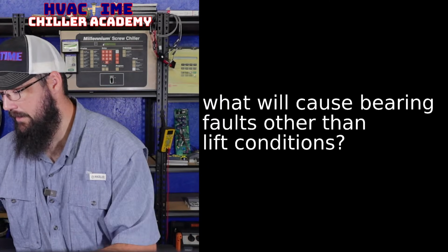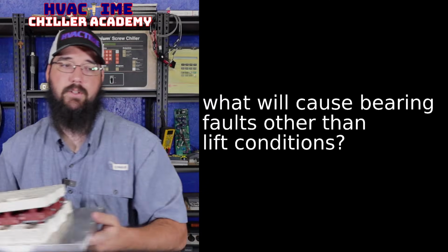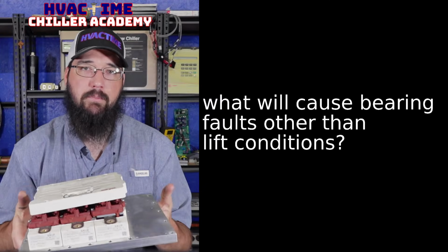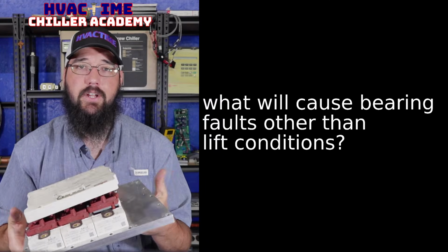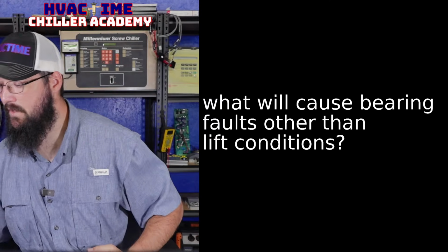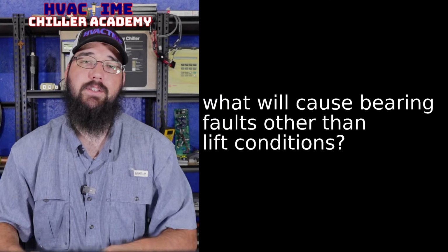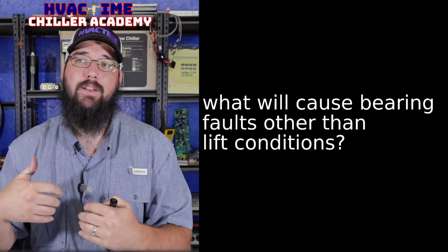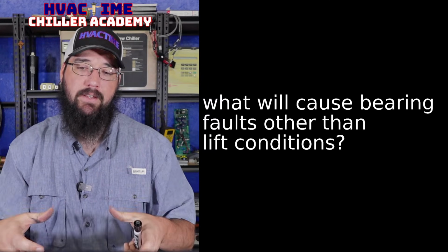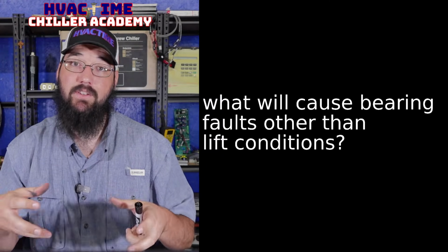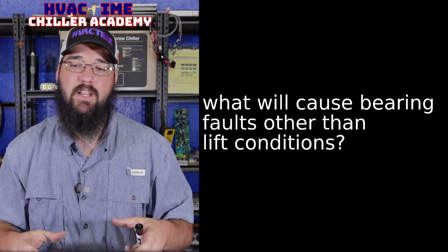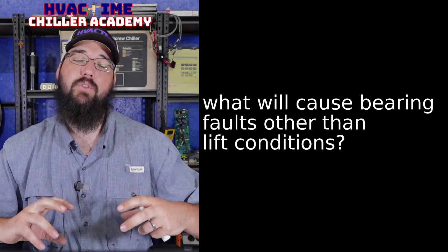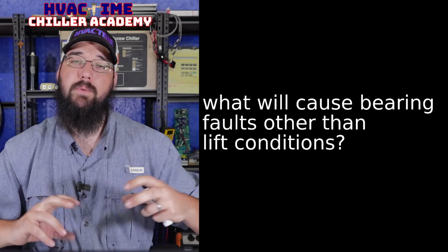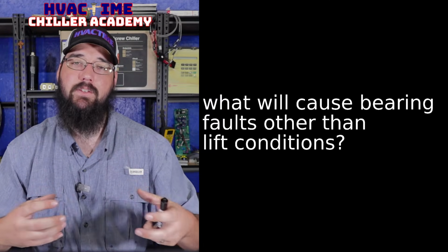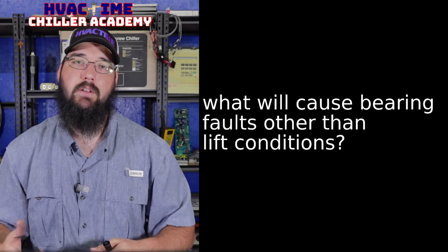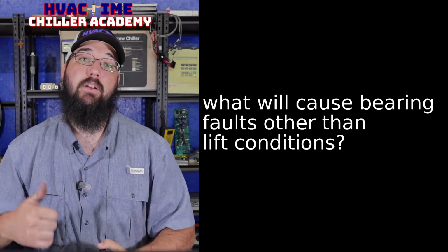All right, so I've got one right here. This is an actual inverter out of a Turbocor. We were playing with this earlier in the stream, so you can go back and check that out later if you want. But what will happen is as the inverter begins to get weak and begins to not output correctly, it's not going to maintain a stable field inside of the stator. And as that field becomes unstable, it allows the rotor to have more movement in it. And that movement is going to be sensed as bearing instability, and eventually it's going to become unstable enough that it will cause the bearings to trip out.